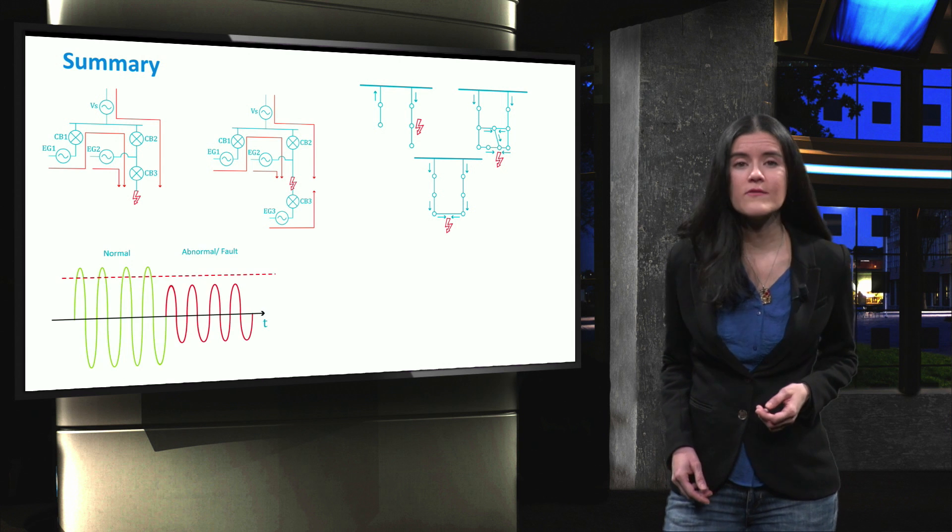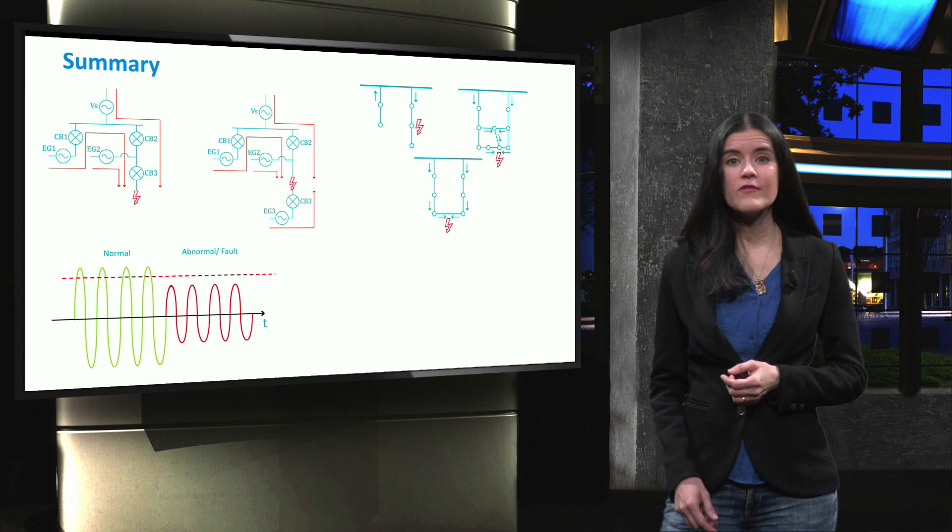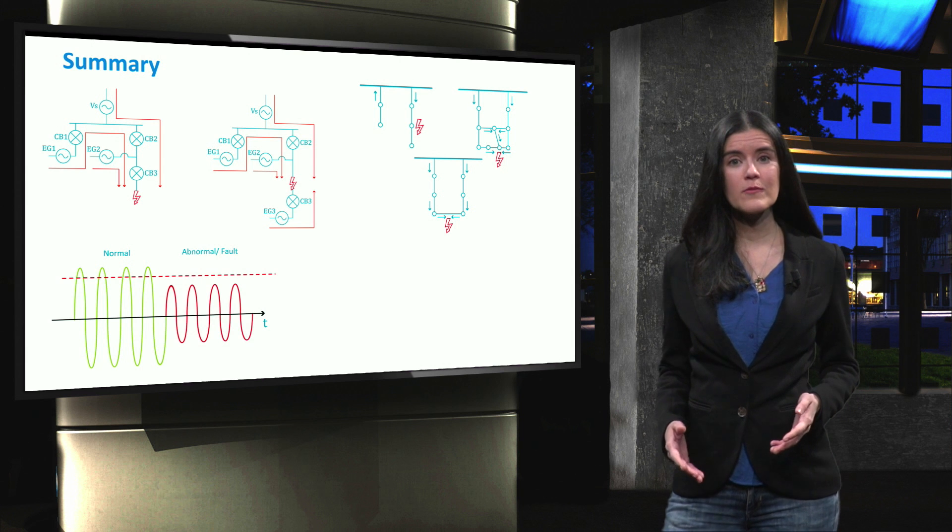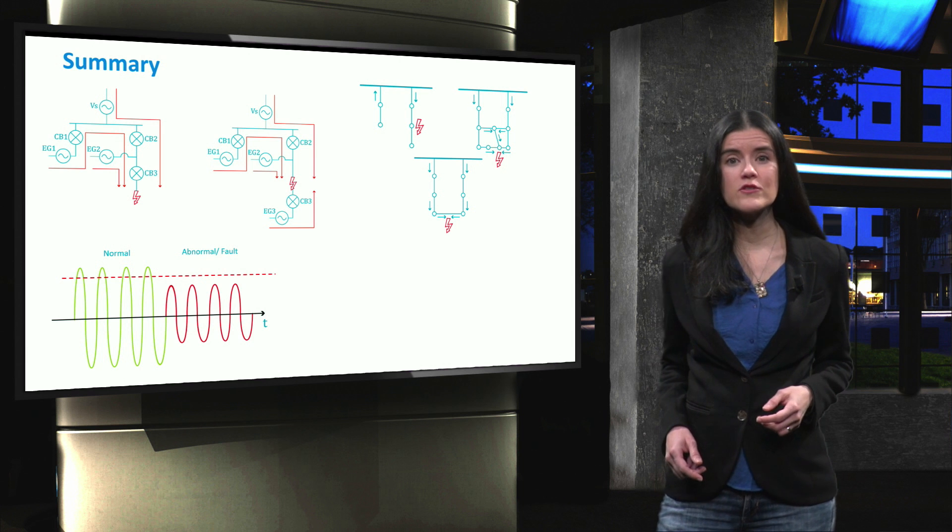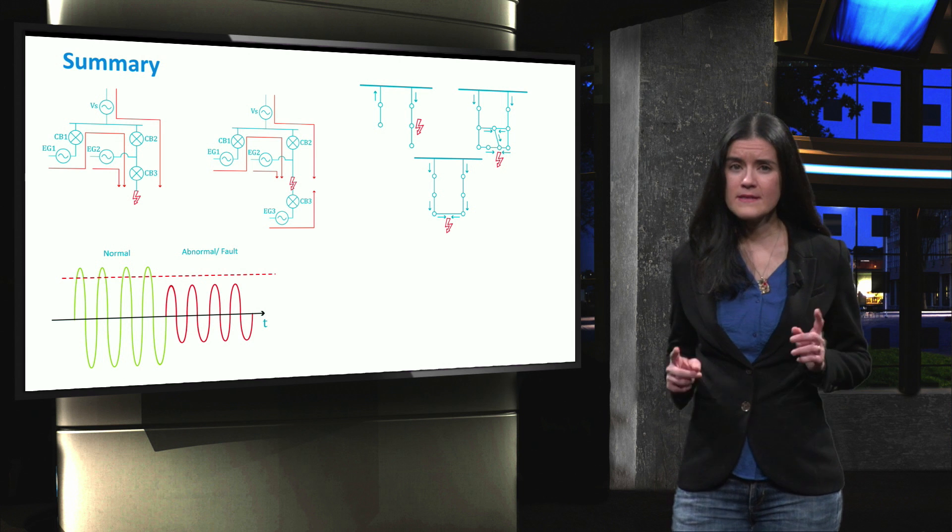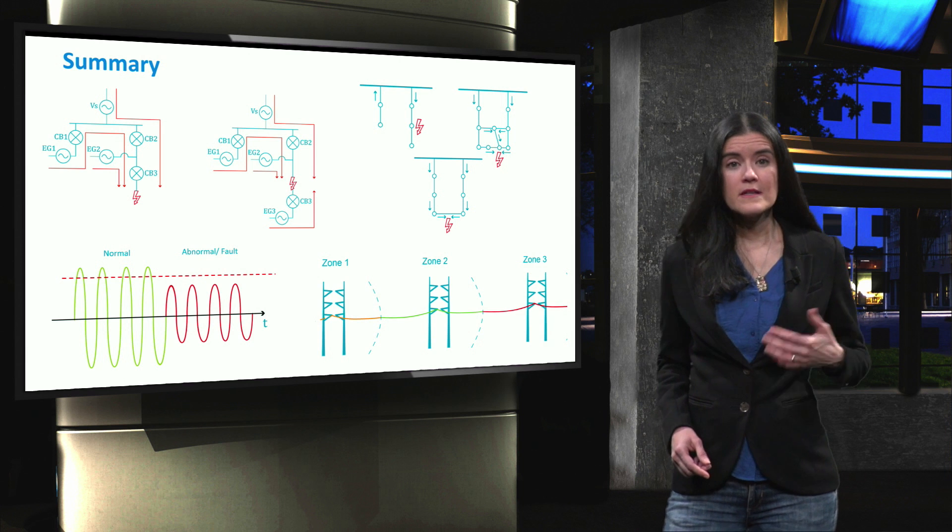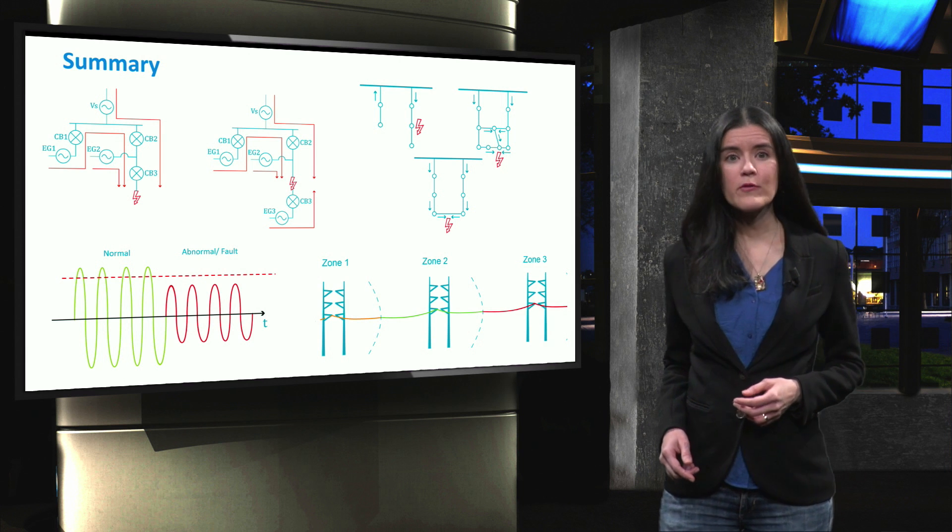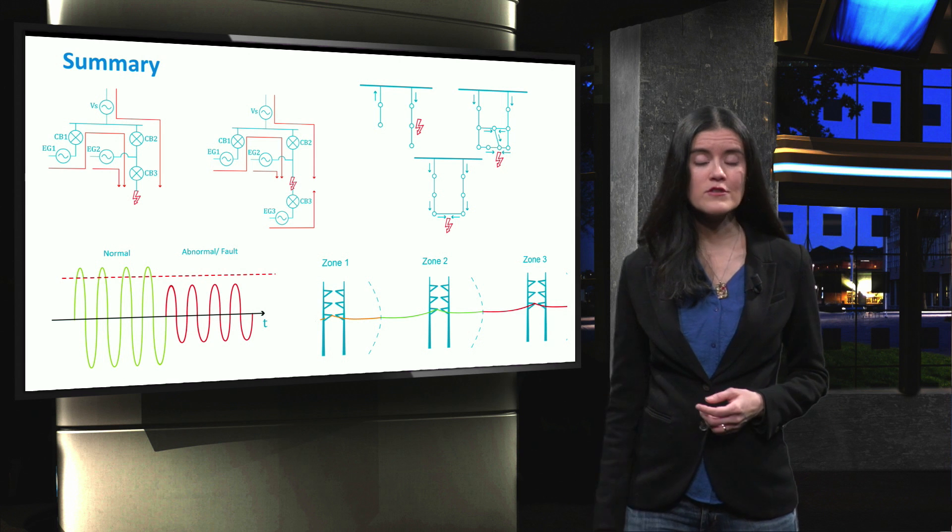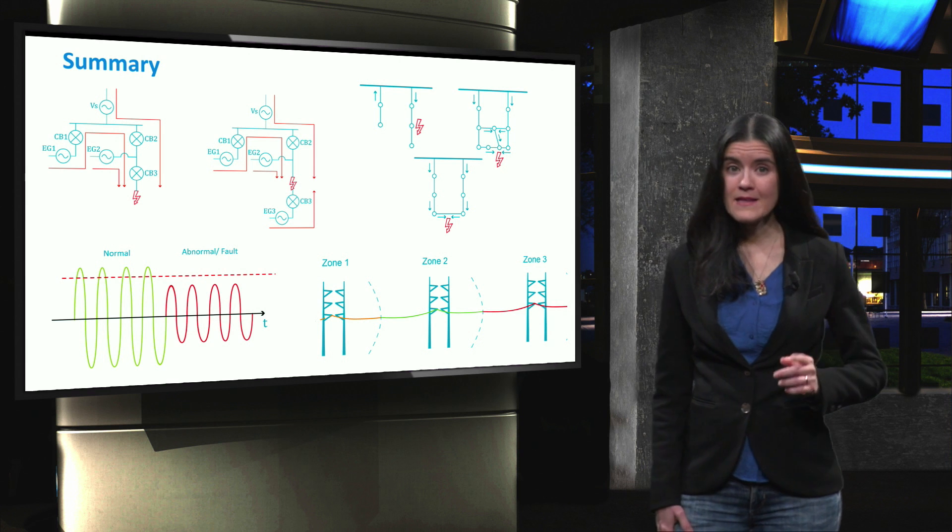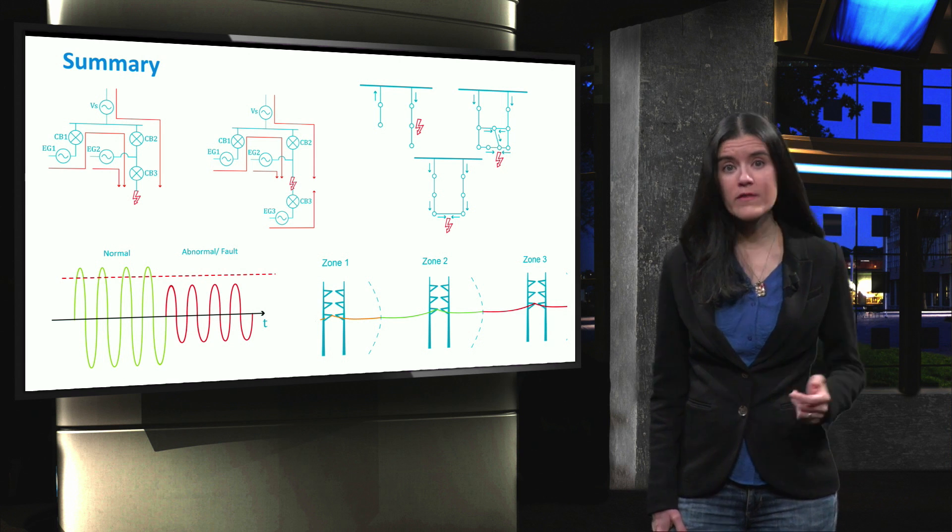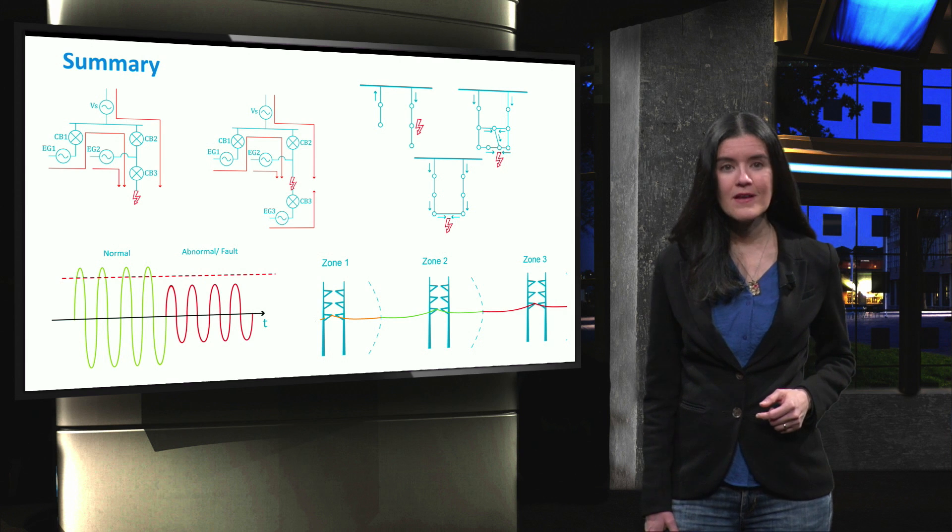We also looked at two protection methods. The first one is the voltage-based protection method, in which any significant drop in the RMS voltage value measured results in the intervention of the control system. The second method is the distance protection method. This provides a good backup for neighboring protection devices by sensing faults in its zone. In the next video, we will go over some other protection methods in microgrid. See you there!